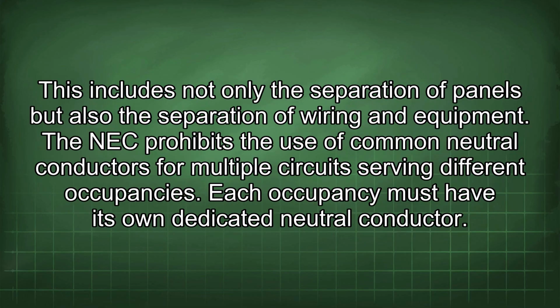This includes not only the separation of panels but also the separation of wiring and equipment. The NEC prohibits the use of common neutral conductors for multiple circuits serving different occupancies. Each occupancy must have its own dedicated neutral conductor.